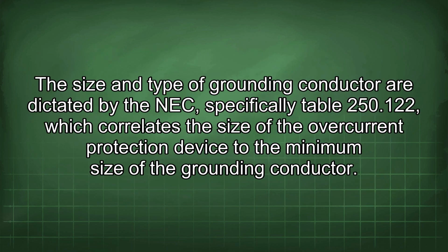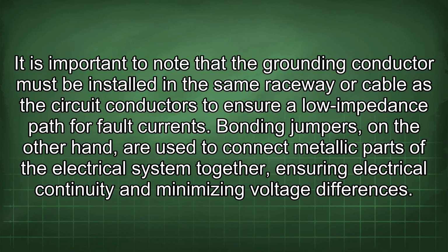The size and type of grounding conductor are dictated by the NEC, specifically Table 250.122, which correlates the size of the overcurrent protection device to the minimum size of the grounding conductor. It is important to note that the grounding conductor must be installed in the same raceway or cable as the circuit conductors to ensure a low impedance path for fault currents.